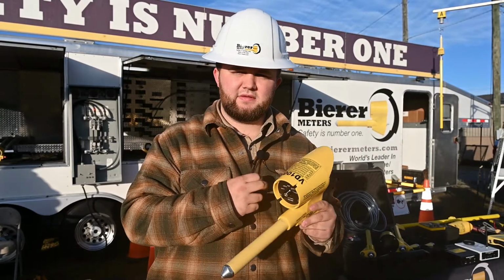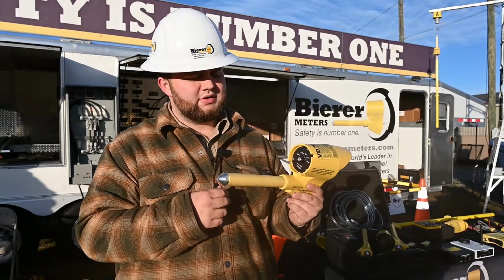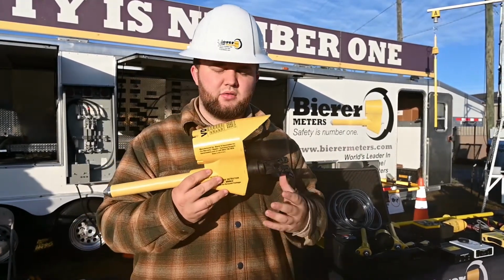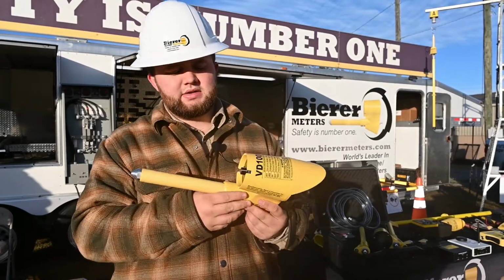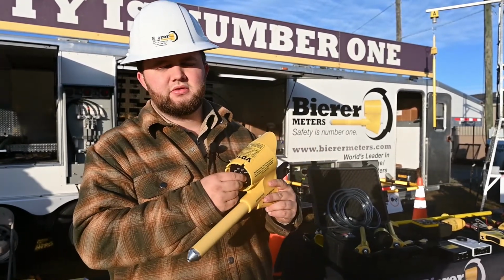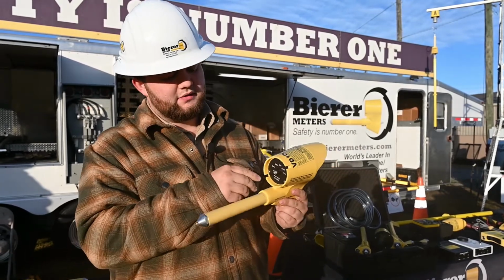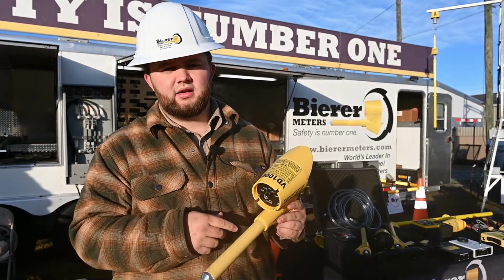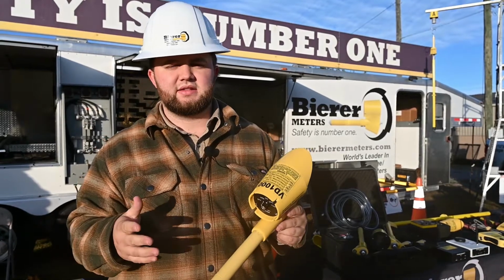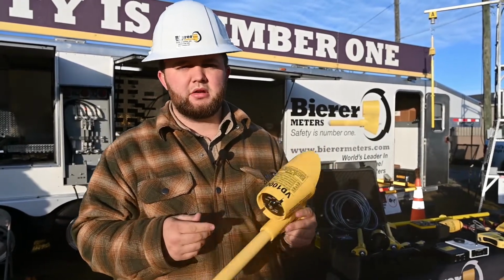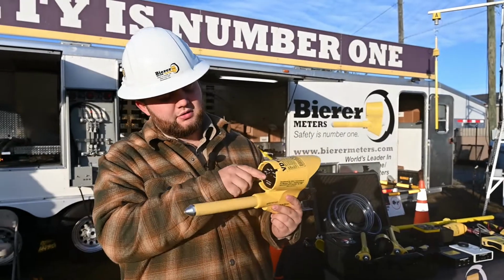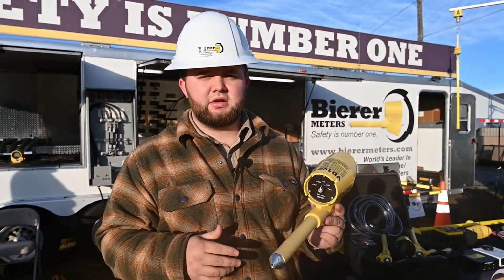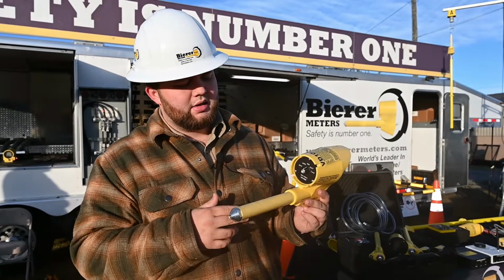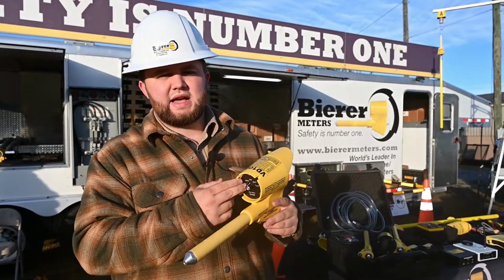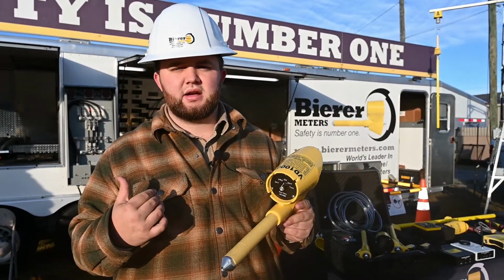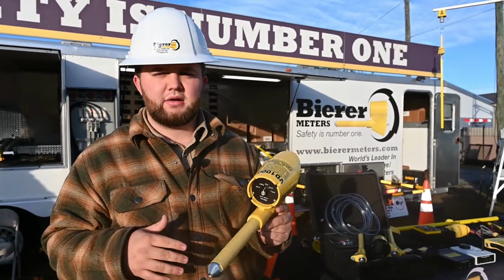That's the most sensitive setting of these tools. So the tool, again, it has to wirelessly couple to the ground. So each time you scale this tool up, it's going to be more sensitive. So if you use the tool in the wrong setting, or if you don't realize the particular scenario you're in, say maybe you're in a substation and you're using the tool in OH because maybe you're 20 to 25 feet off the ground. But even though that potential's high in a sub, there's a lot of nearby ground planes. There's a lot of grounded structures.